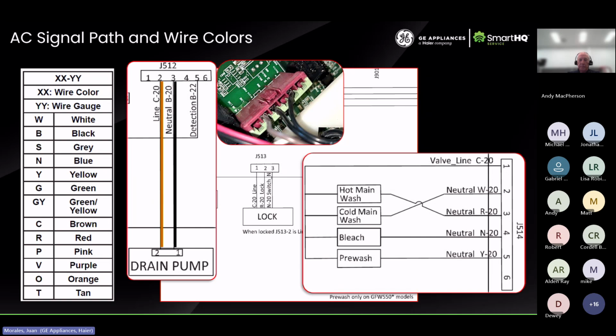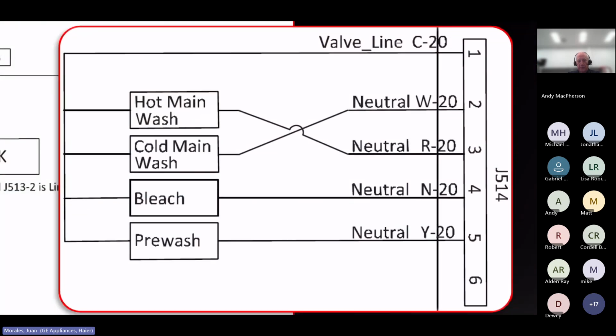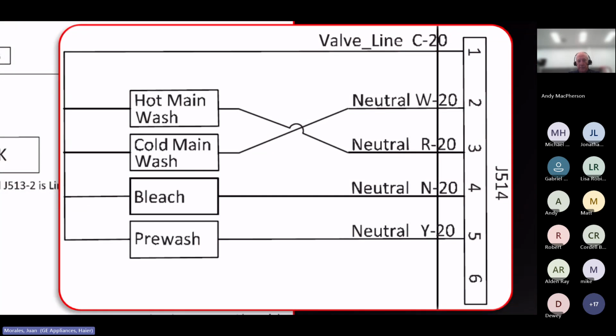So let's go ahead and dive in and zoom in here to the water valves. You can see that the water valves are connected to connector number J514, a 6-pin connector. Pin number 1 is what's common to all the valves. If we follow that line, we already know what C stands for - C is brown. So that brown wire provides line voltage to every single one of the water valves. Now, on the other end, to complement the circuit, there has to be a neutral, and those come from the rest of the pins on connector J514.